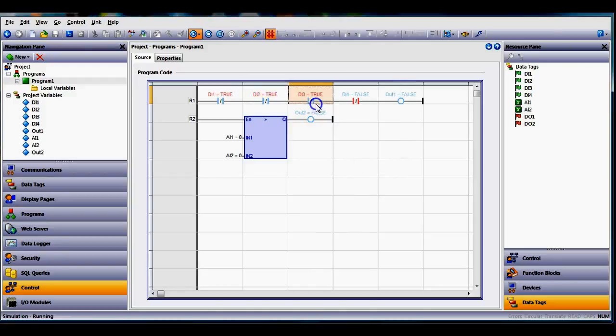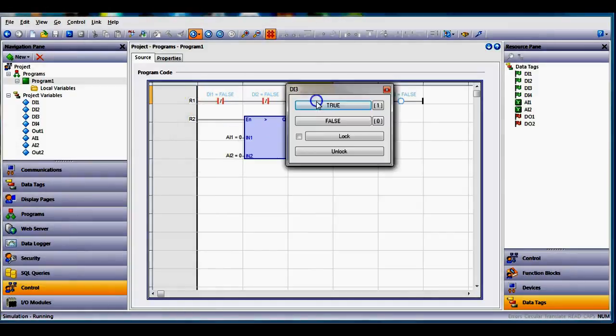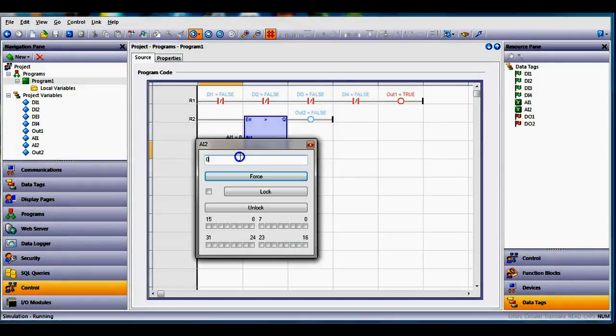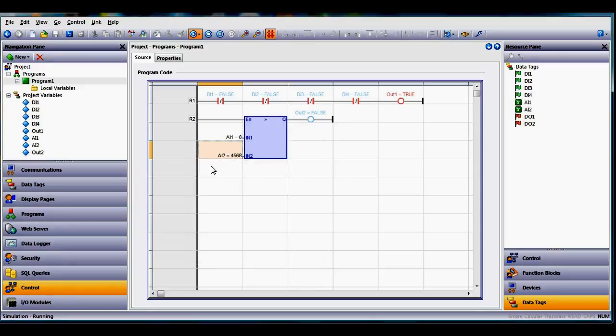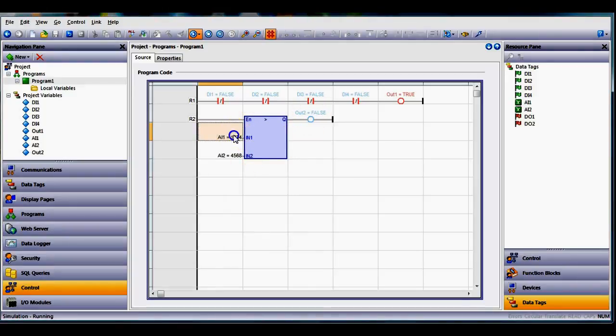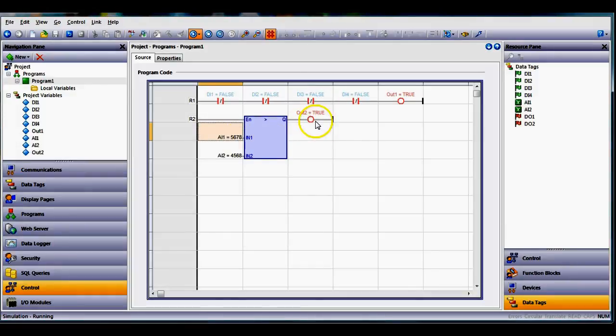And you can see that I'm going through this complete AND statement here. And it should be running. So true, true, true. Okay, that's false. Let me turn them back off. Okay, that makes that statement true. I was reading that wrong. Sorry about that. And then if I go here, let's say that I change this analog input here to be 4, 5, 6, 7, just something thrown out there. Notice when I change this one to something less, the output stays false, but I've changed this number to, say, 5, 6, 7, 8. Now it's greater, and you can see that goes true. So I just tested the logic offline here, and it should be fine.